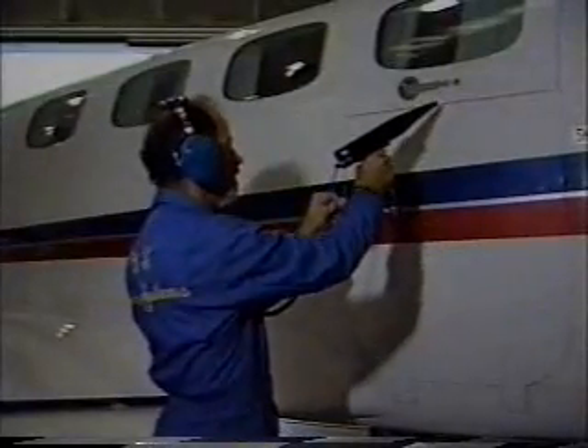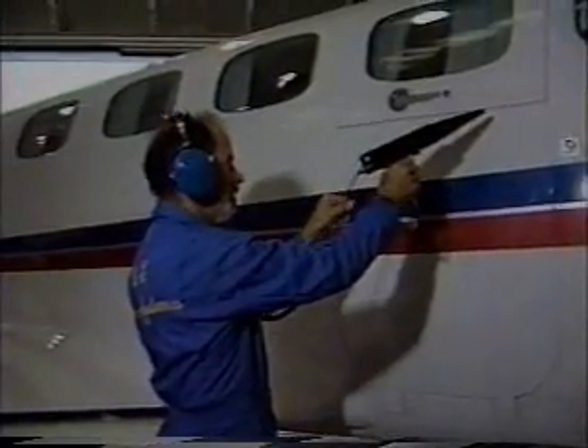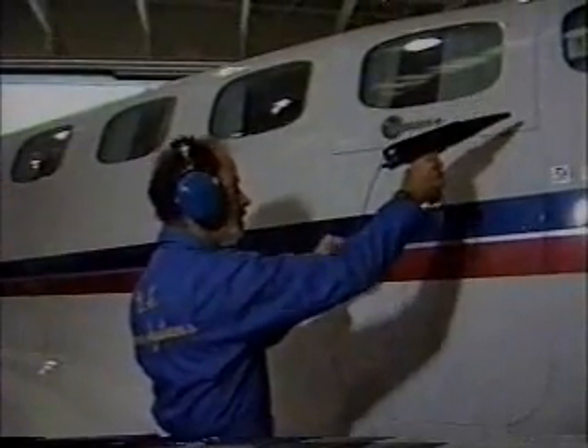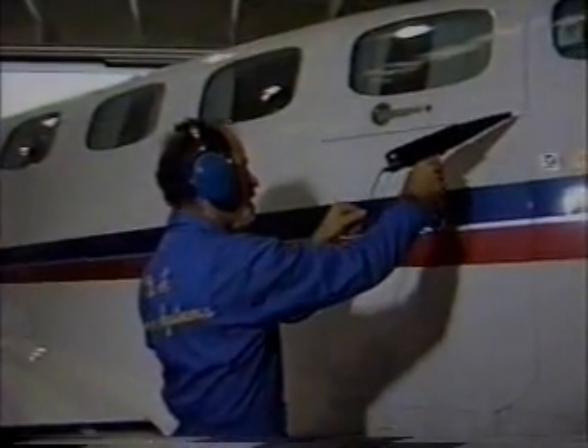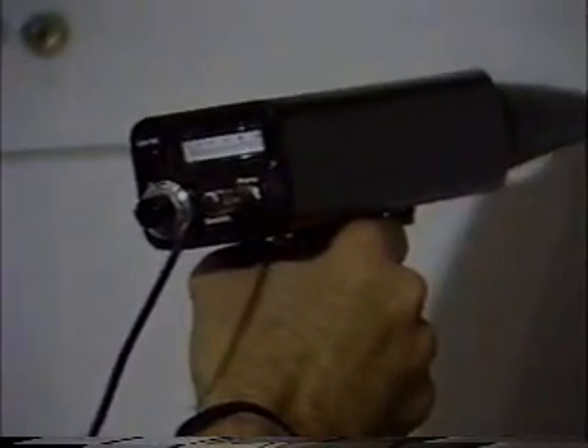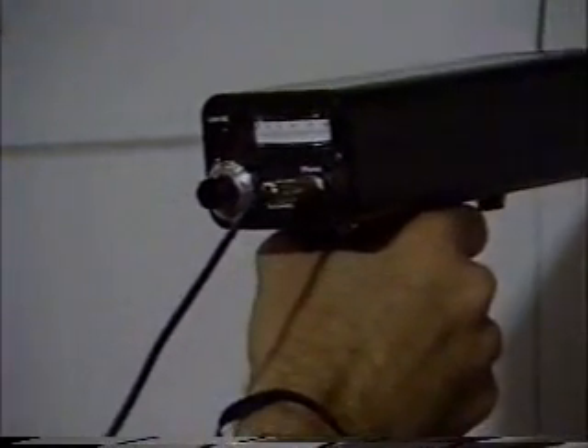Use the rubber focusing probe to narrow the field and reduce the sensitivity to pick up only very fine ultrasonic signals. Recognizing the sounds of leaks comes easily with practice and is also made easier by watching the ultraprobe's meter as it responds to varying signal strengths. Confirm the leak by moving the probe back and forth over the site.